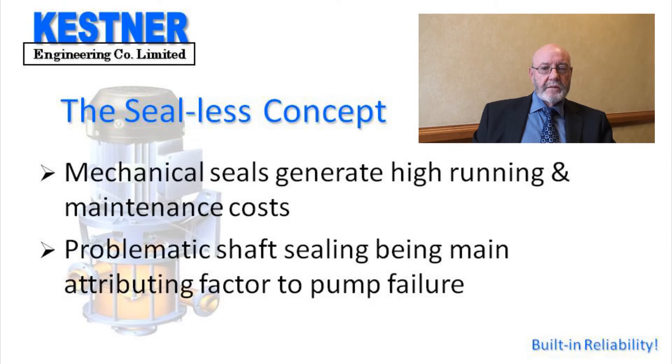Because shaft sealing — be it a packed gland or the modern mechanical seal — is the Achilles heel of the horizontal chemical pump and is responsible for 90% of maintenance and repairs, the seal-less concept was born.